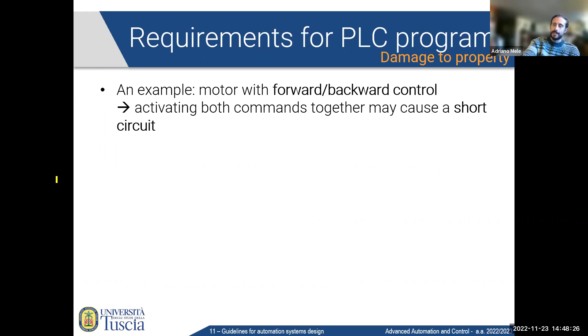So, contactors, relays, and other control devices that control elements of the machine and that can cause a hazardous condition when actuated at the same time shall be interlocked against incorrect operation. And again, also here, proper coordination shall be ensured by suitable interlocks. And also here, where a failure of a mechanical brake actuator can result in the brake being applied when the associated machine actuator is energized, and a hazardous condition can result, an interlock shall be provided to switch off the machine actuator. So there are situations in general, I mean, we don't want to be super specific here, but just know that there are situations where you want to put into action either physical or software interlocks to avoid that incompatible sequences are executed together. That's one of the most common safety concerns you want to take care of.